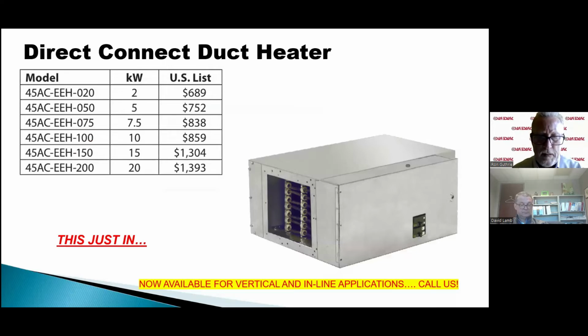All right. This is also available. The installation instructions, depending on when it was shipped, may not say it, but this is also available to be mounted vertically on top of a vertical air handler. And it can also be used in line, but to use it in line, you're going to have to adapt the entering side, which is meant to mount right up to the air handler. What goes on this outlet end that you see in the picture there is the plenum adapter that you would normally put on the outlet of the air handler. So you still need that adapter. You just, instead of putting it on the air handler, you put it on the end of this.